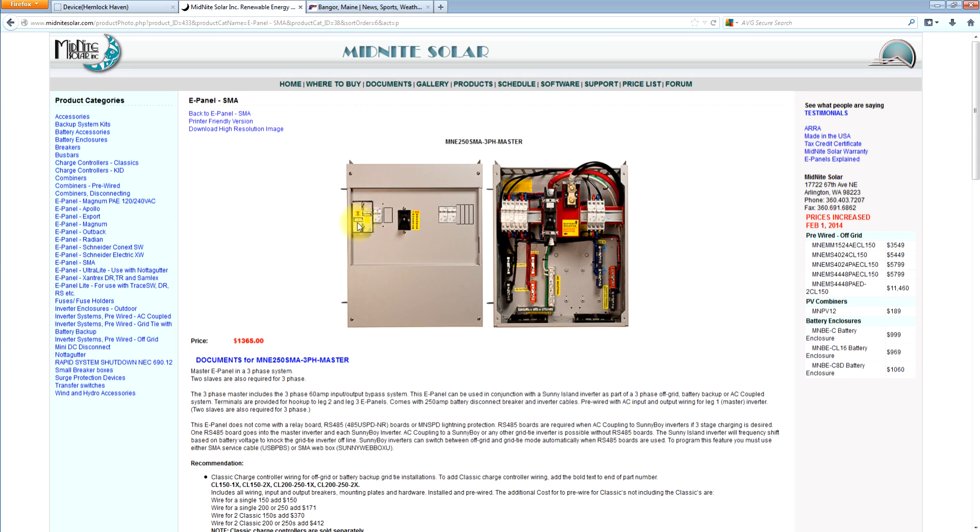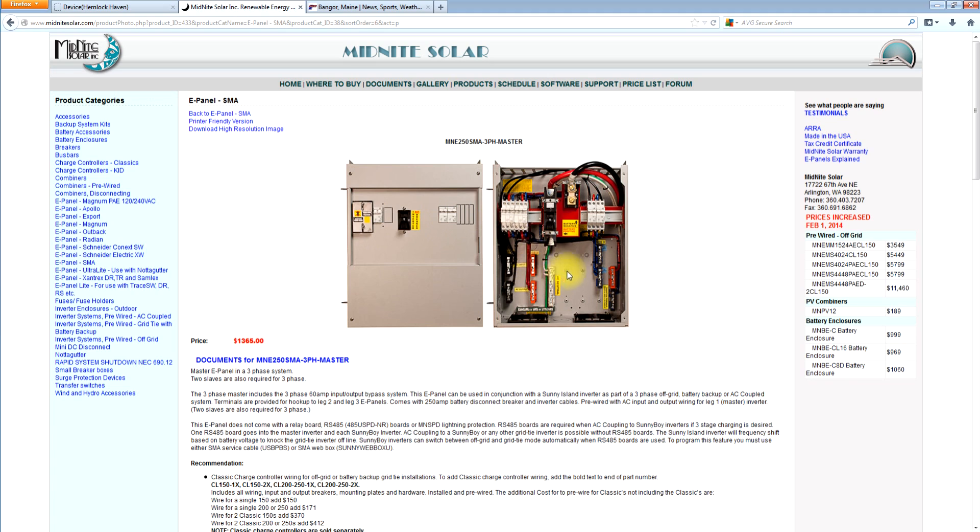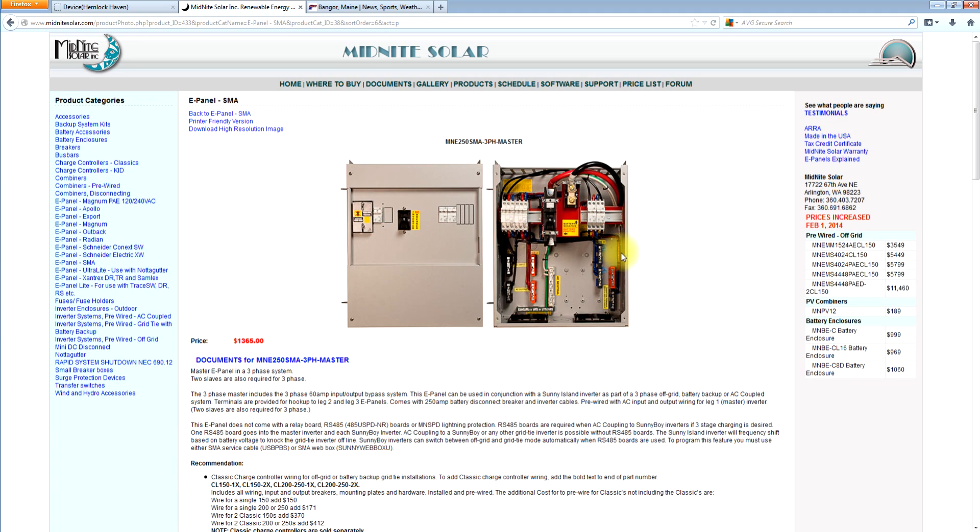So this picture over here is actually incorrect. I'll have to note that and get that fixed. As you see here, there's two three phase breakers. And what happens is that that gives you a three phase bypass, instead of a two pole bypass like shown. So it works the same as all of our E-Panels. You have a bypass slider. Up is invert. Down is bypass. If something should happen to the Sunny Islands, you can throw the bypass slider into the bypass position, passes the utility grid straight through or the generator straight through and powers the loads.